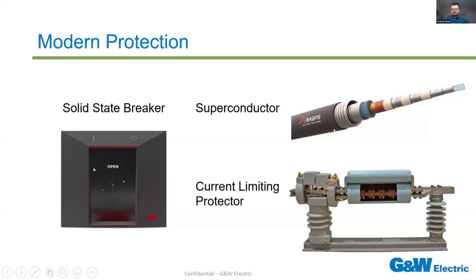in order to bring it down to a superconductive, low resistance state. At the bottom right, you have the G&W current limiting protector, where you can see inside what's called the G&W interrupter, where the pyrotechnic charges are laid in those notches, to be electronically triggered and respond to a specific high-level fault. Once those detonate and that bus bar gets blown apart, copper gets folded back over those larger copper chunks. All that fault current then gets commutated through those current limiting fuses. Those melt and clear. That fault gets completely eliminated in 1/4 to 1/2 of an electrical cycle.